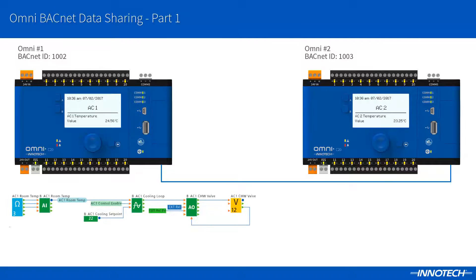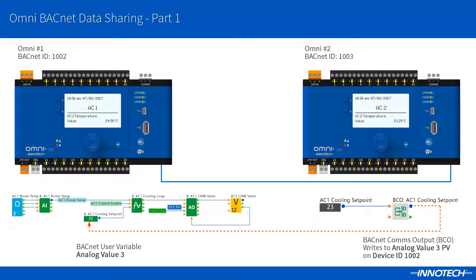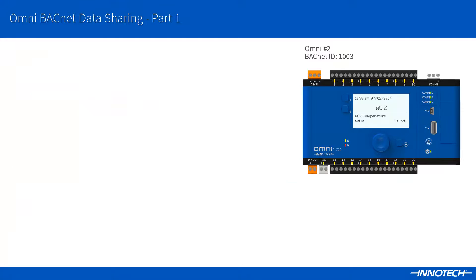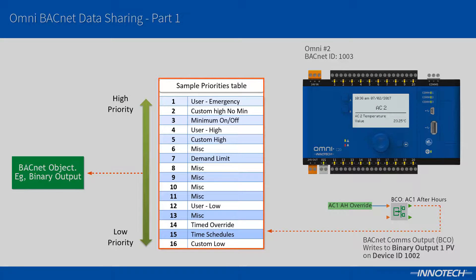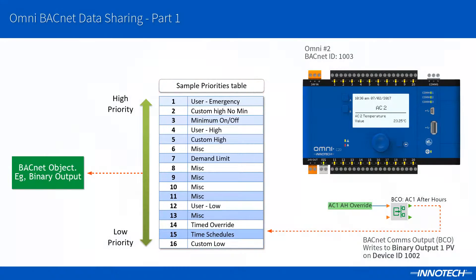In this example we are demonstrating that using the BCO block we can write to a remote BACnet object's present value. In this case I am writing to the present value of the cooling setpoint on the remote OMNI. This is configured as an analog value block which is a BACnet user variable. The BCO is configured to write to the present value of this object. An important item to note in regards to the BCO: you can configure a priority to write the present value at. This consists of a priority array, and for third party devices this may need to be confirmed with the device manufacturer as to which priority to write at.